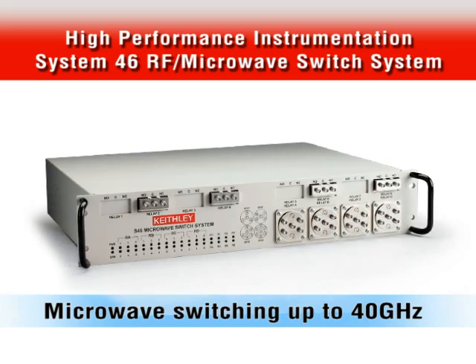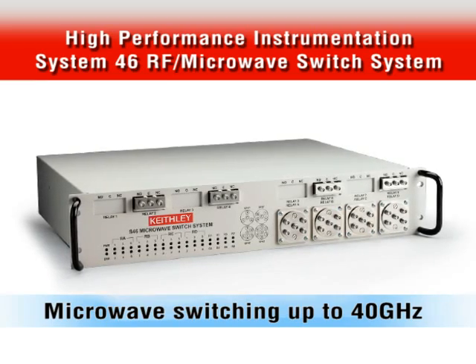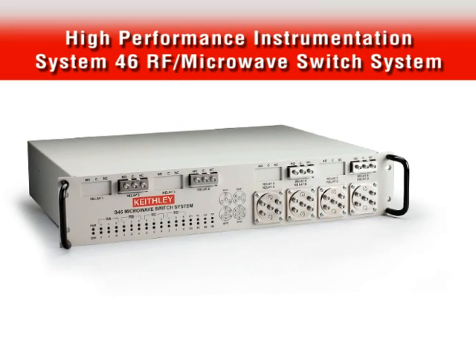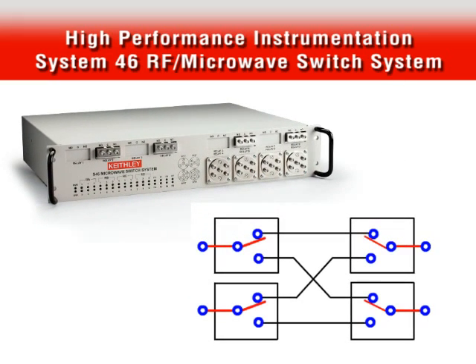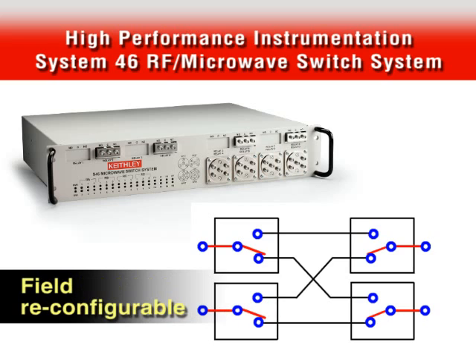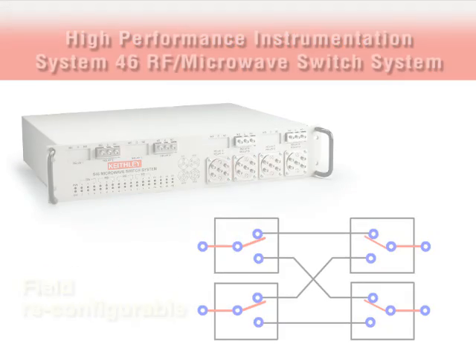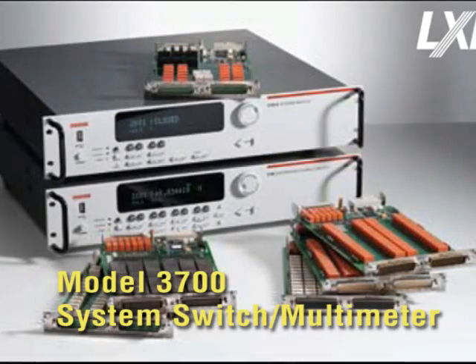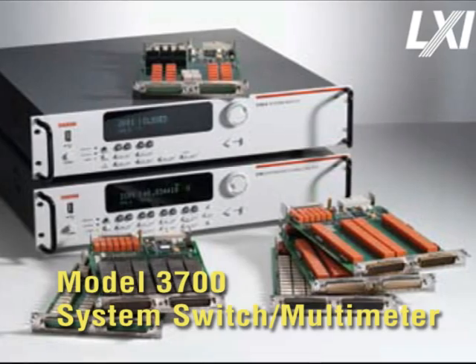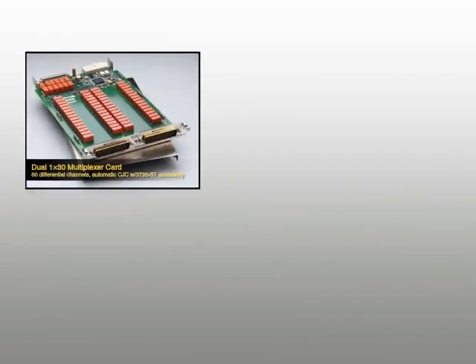and get flexibility such as a field reconfigurable system expandable up to 32 switching channels, use of either terminated or unterminated relays, and monitoring relay life with the contact closure counter.